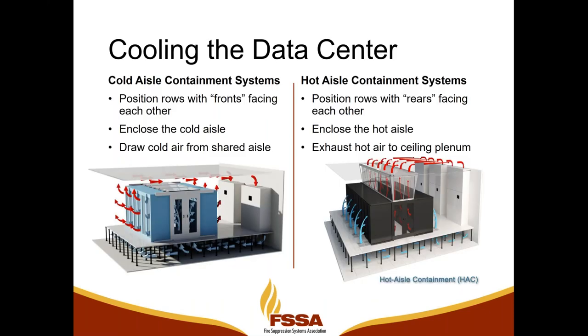In a modern data center where aisle containment is deployed, there are two strategies. There's cold aisle containment, where we build a box around the cold aisle, so a lot of times we place a roof inside of our room. And then there's hot aisle containment, where we duct the hot air to a plenum or to a duct and then back to the cooling units for the data center. So let's take a little bit of a closer look at those.